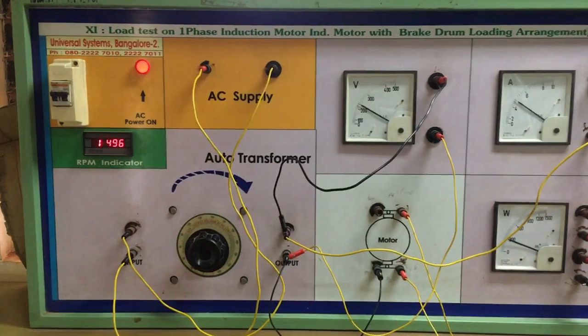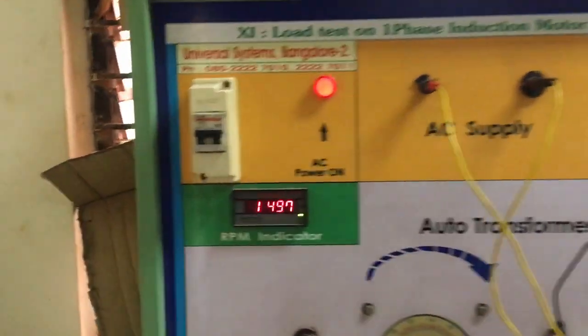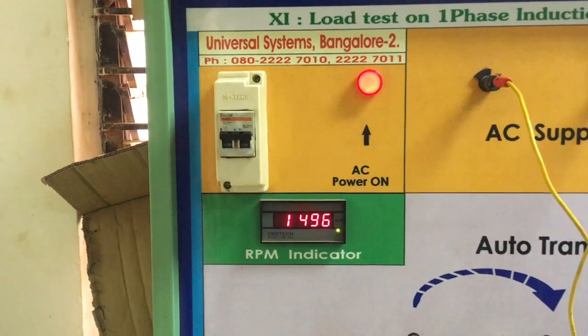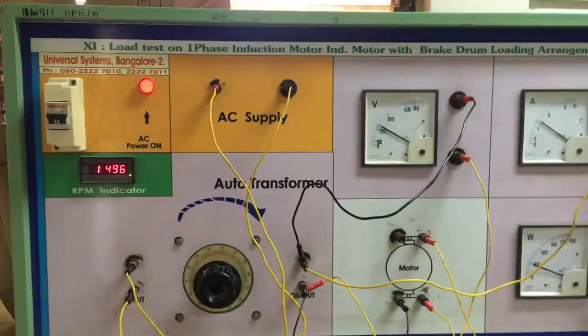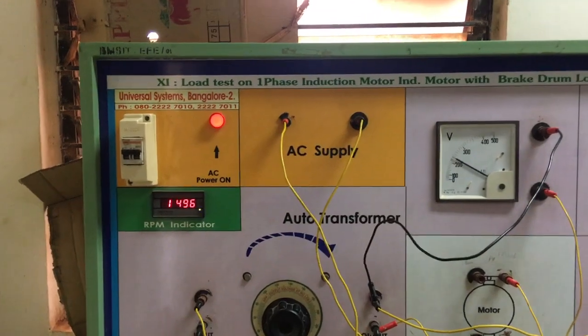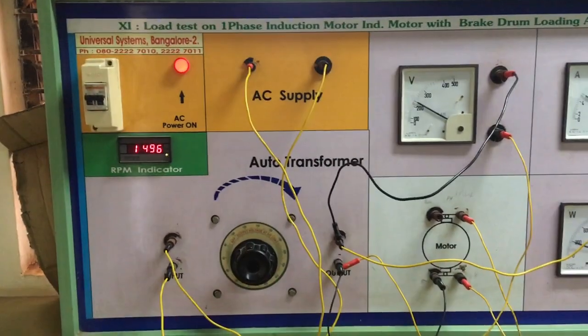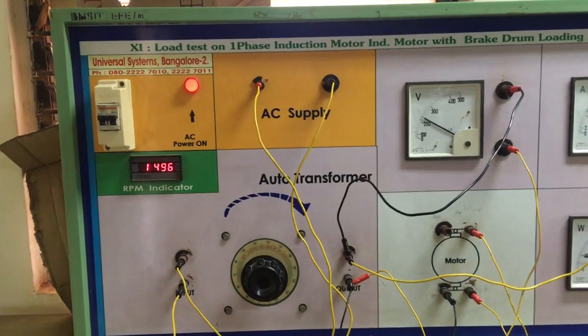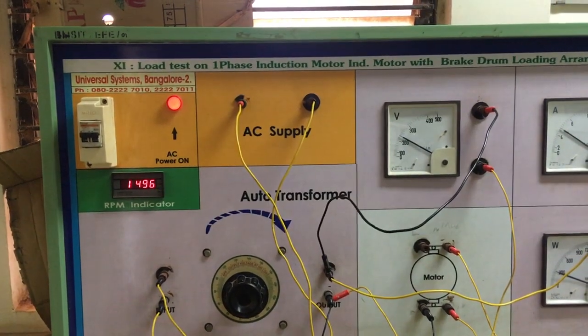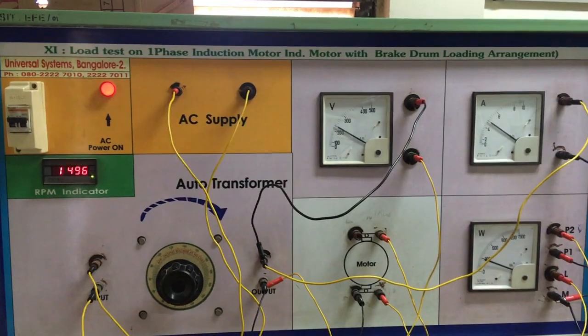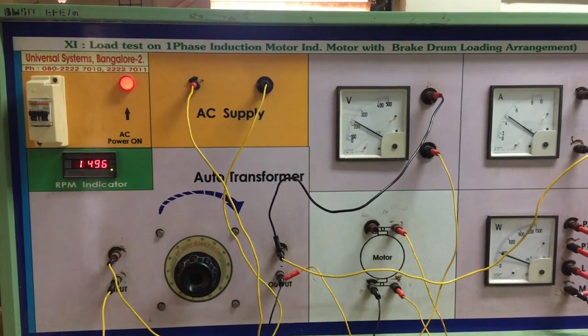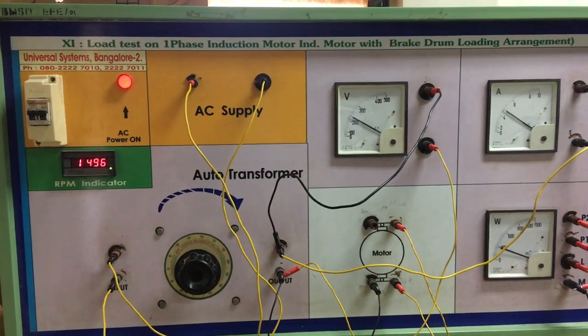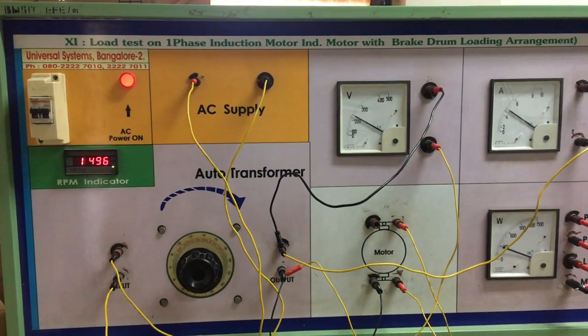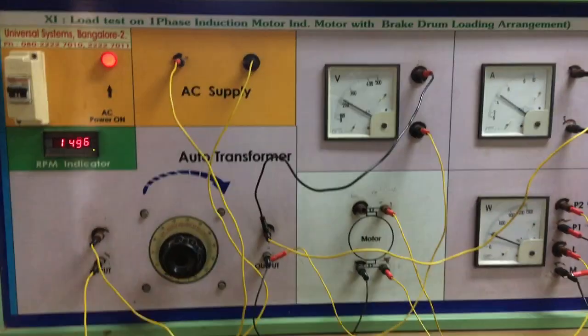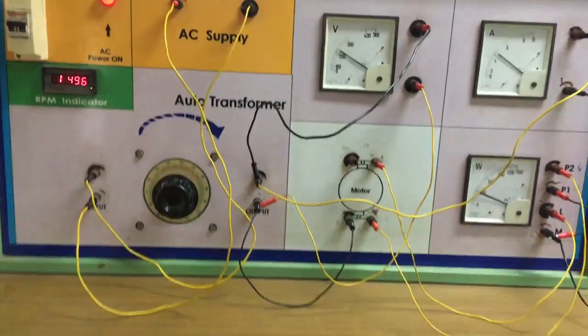Now the speed of the motor is 1496 RPM, 1497 RPM, very near to the rated speed. So we will note down the values. No load voltage is 230. Line current is 4.4. Input watts is 300 watts. F1 and F2 will be 0, because I haven't loaded it, and speed is 1496 RPM.